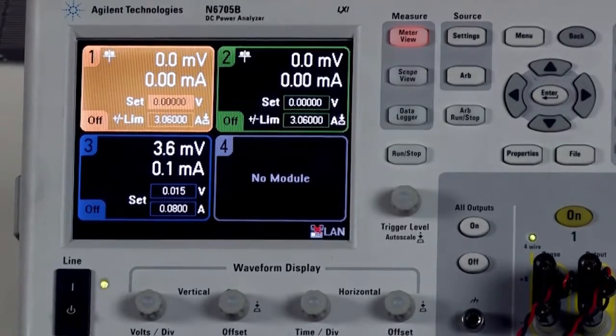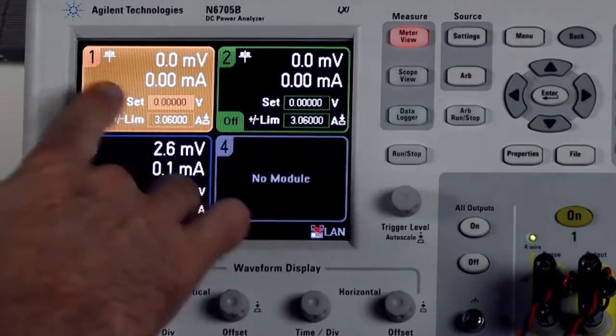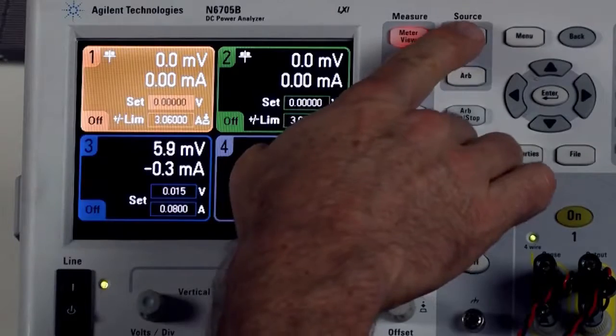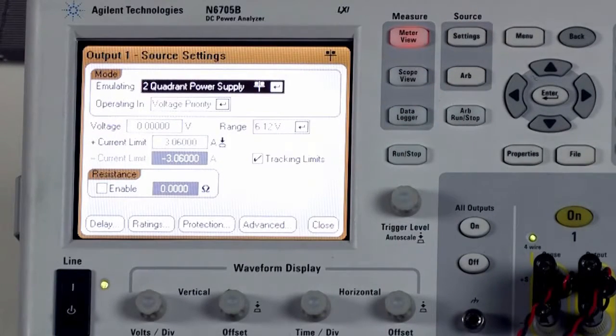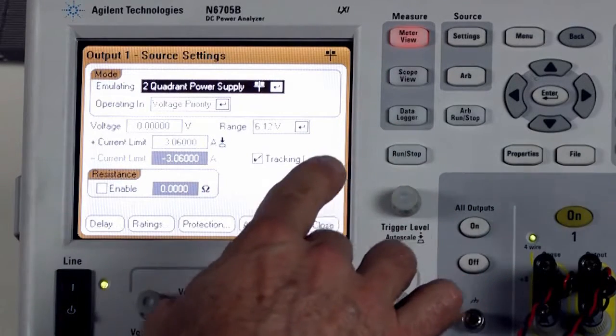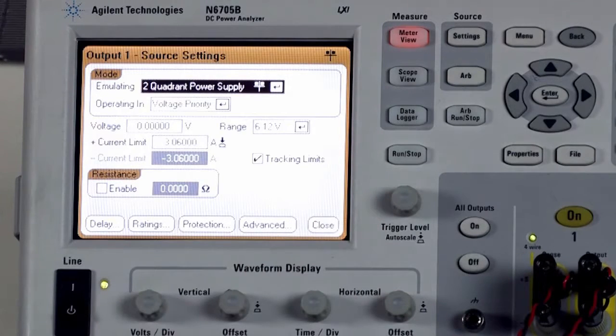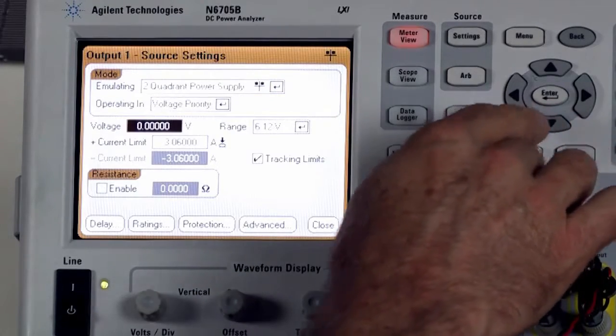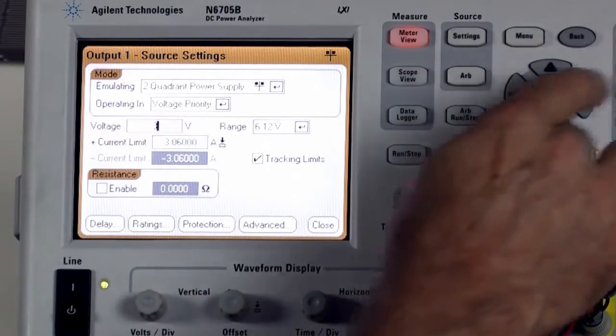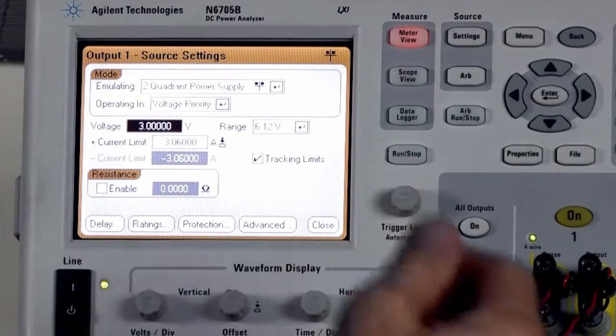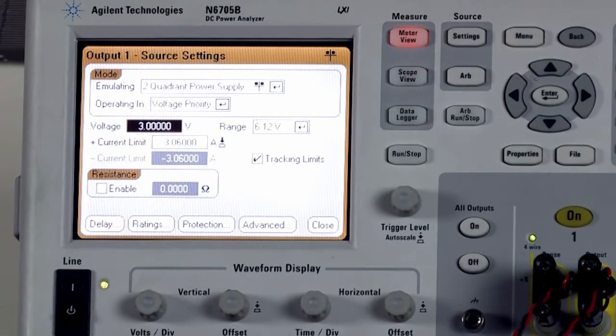Now moving on to step 2, we need to configure the SMU. We already have number 1 highlighted. We're going to hit the settings key and look at some of the basic configuration. This is a 2-quadrant power supply, which allows you to sink or source current with a positive voltage. We're not worried about that or most of the settings, but what we do want to do is simulate the 3-volt battery in our pulse oximeter. So I'm going to use the arrow keys to toggle down to the voltage section, select 3 volts and enter that. If you wanted to, you could change the current limit, but I'm going to leave that as is.